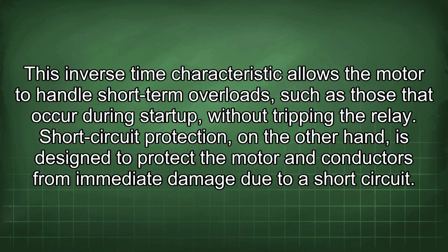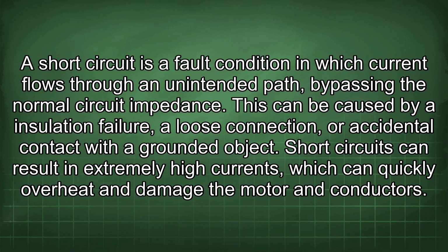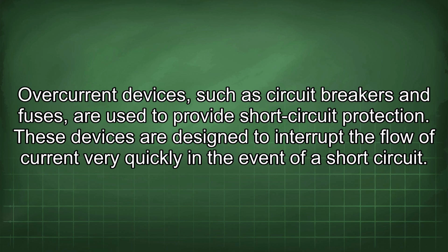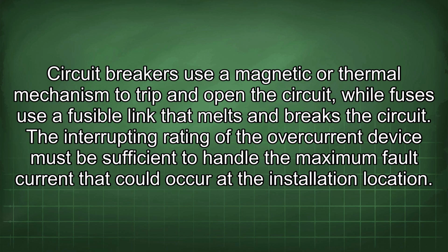the relay. Short-circuit protection, on the other hand, is designed to protect the motor and conductors from immediate damage due to a short circuit. A short circuit is a fault condition in which current flows through an unintended path, bypassing the normal circuit impedance. This can be caused by insulation failure, a loose connection, or accidental contact with a grounded object. Short circuits can result in extremely high currents, which can quickly overheat and damage the motor and conductors. Overcurrent devices, such as circuit breakers and fuses, are used to provide short circuit protection. These devices are designed to interrupt the flow of current very quickly in the event of a short circuit. Circuit breakers use a magnetic or thermal mechanism to trip and open the circuit, while fuses use a fusible link that melts and breaks the circuit.